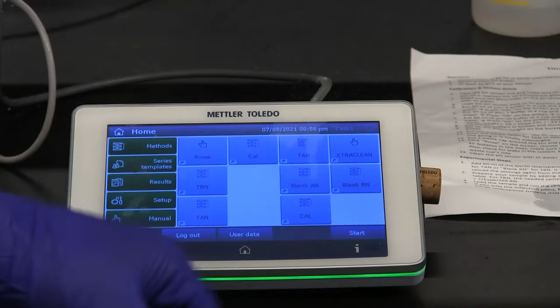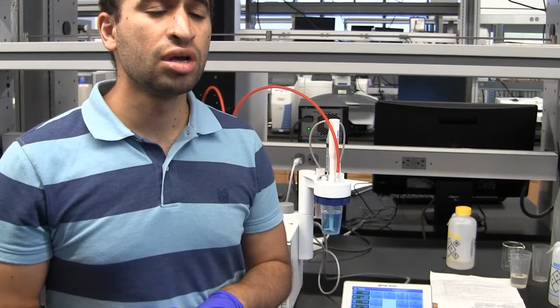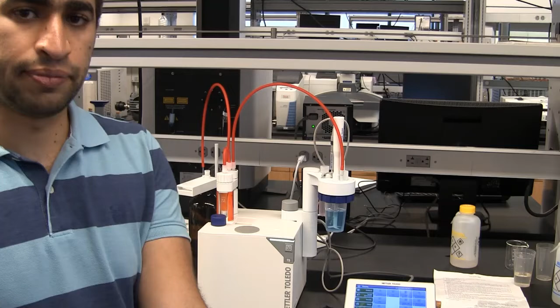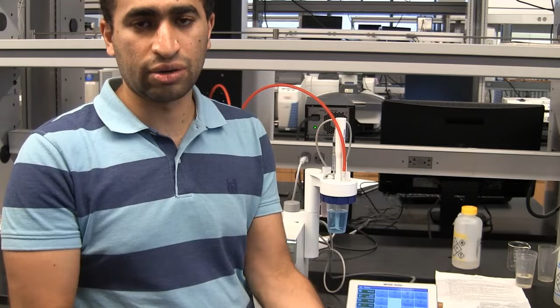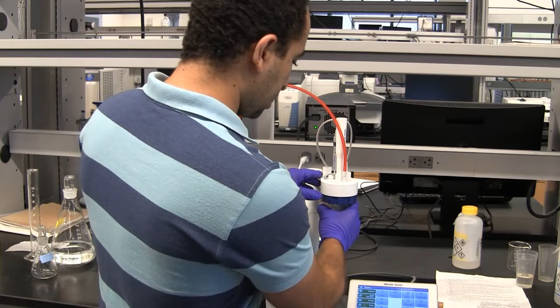So now the calibration is done, we just go home and we start our sample. First things first, we need to do a reference. So our reference will be a 50% isopropanol to 50% toluene, or 1-to-1 percentage. A 60 ml of this, and then we will run it as our reference or blank acid number. After that, we will run our sample, and I'll tell you how to prepare the sample. So just need to take this off, clean the system, and do it.